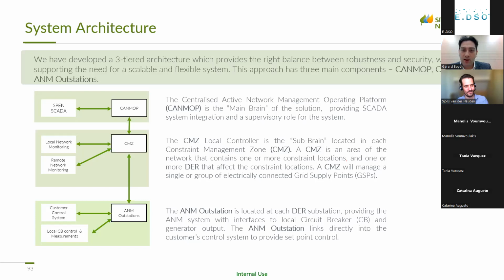We've got a main brain that does all the complex system analysis, and then you've got local controllers, which also have fail-safe modes, as mentioned in the previous presentation. Both the CMZs and the local ANM outstation controllers have fail-safes designed in, appropriate to what impact it could have on the network. So it might be curtailed to zero, or to a lower percentage, but they've all got that programmed in to provide a fail-safe option.